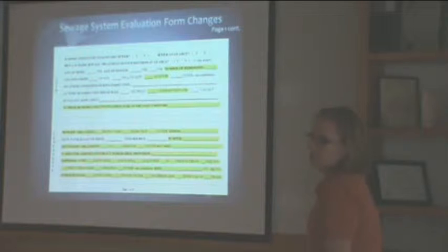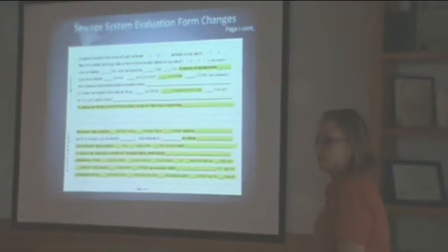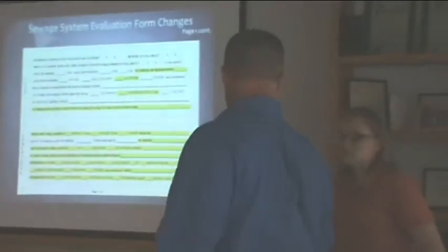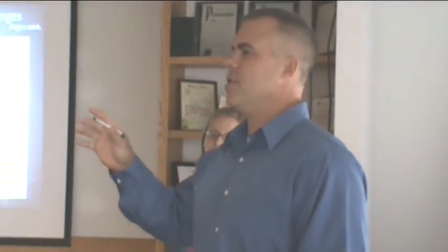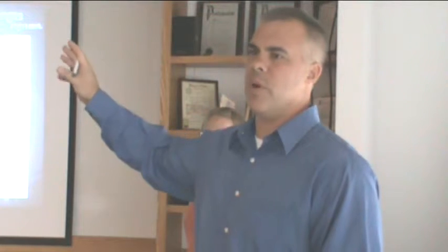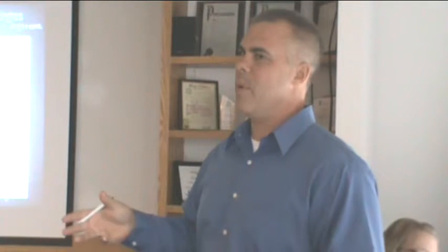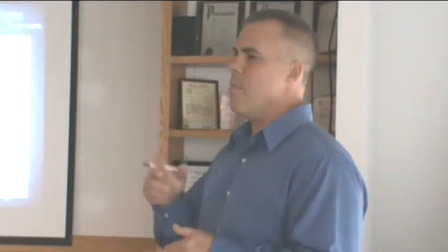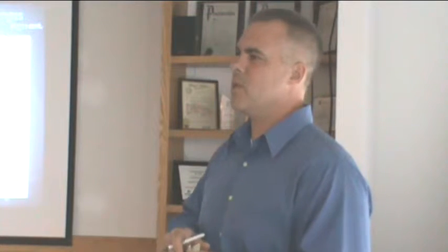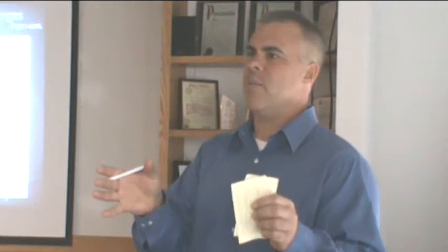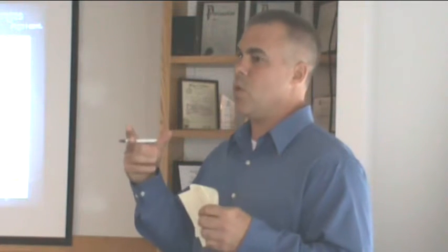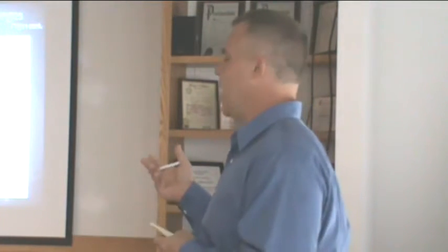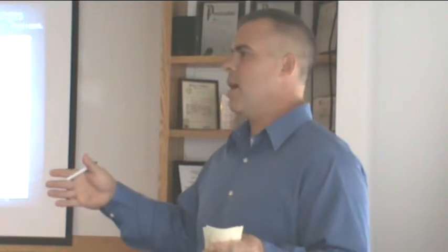Laura, I'm not sure if you're going to address this or not, but one issue on the lift station that we wanted to, were you going to talk about that later? Go ahead. Okay. The lift station, the old system's no big deal. You get it from the low point at point A to the high point at point B. If you're looking at a newer system, which we haven't seen much yet, but I know there's going to be more and more that will be reviewed, mounds and LPP and maybe flood dosing, they're a whole different animal. And if you're not accustomed to it, you need to learn about them. For example, when you inspect an LPP, which a mound actually has in it, that's low pressure pipe.